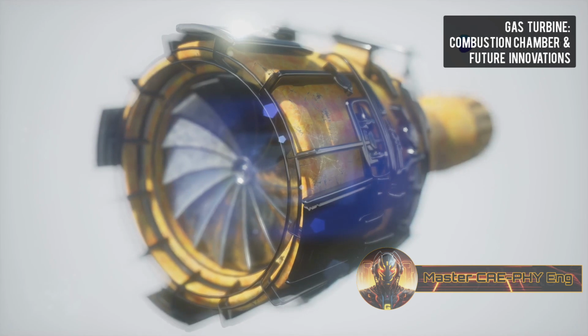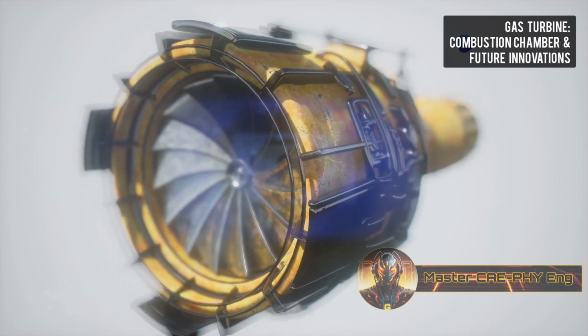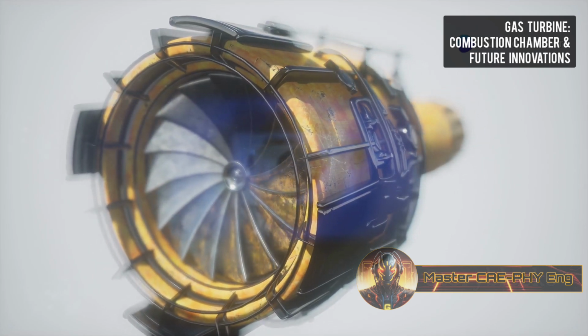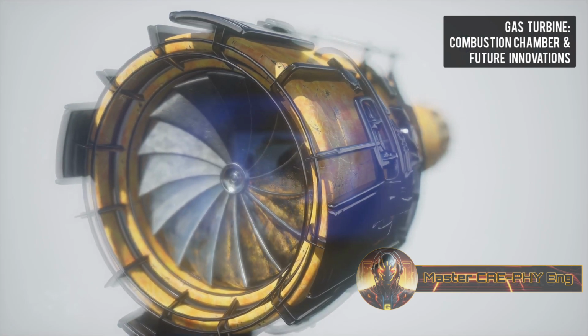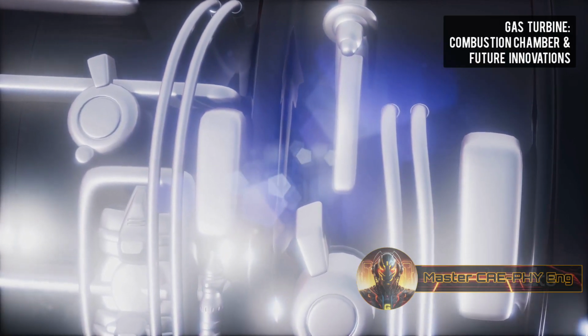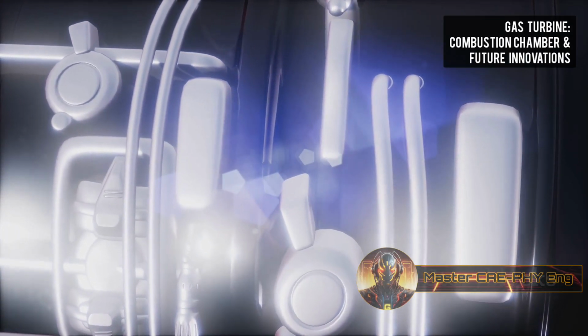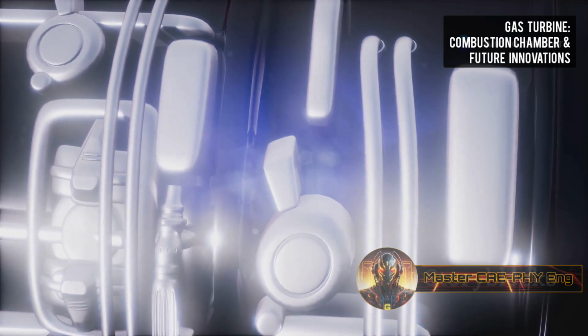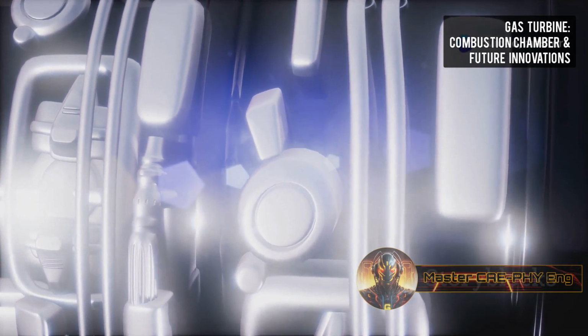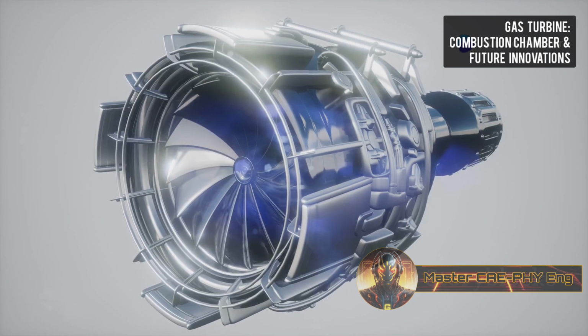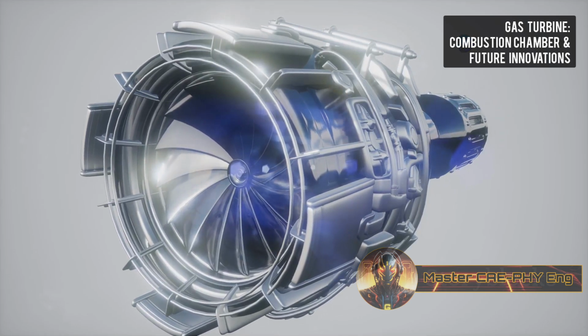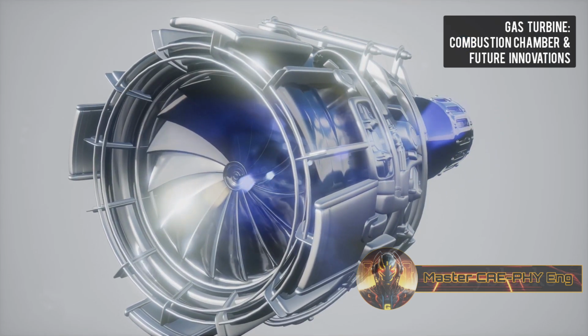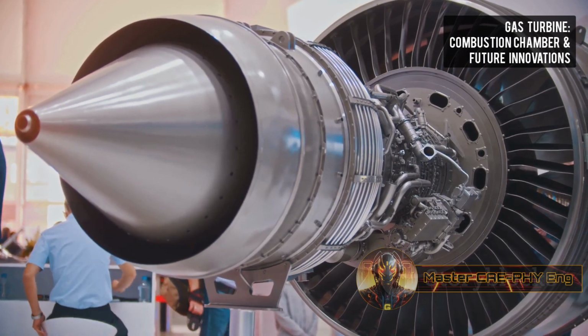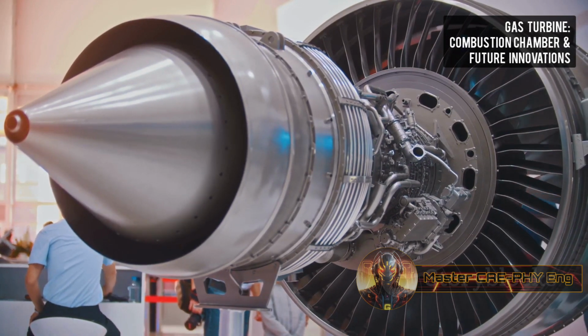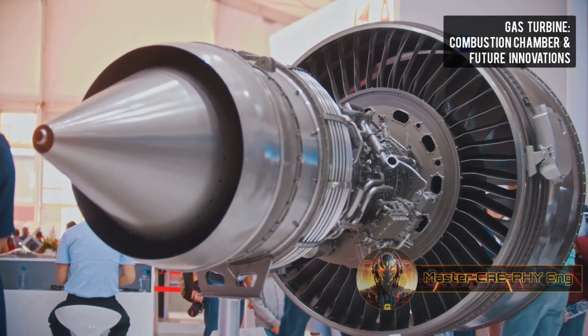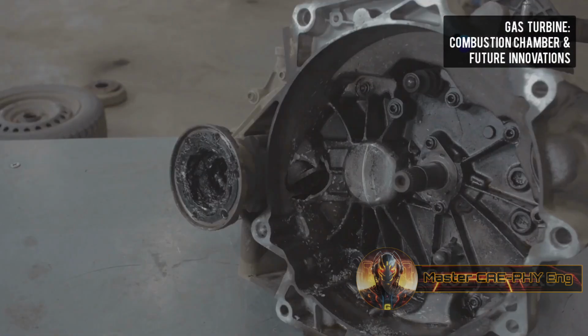The application of thermal barrier coatings, or TBCs, is another critical aspect of material strategy. TBCs are thin ceramic coatings, typically yttria-stabilized zirconia, applied to the hot gas side surfaces of combustor components. These coatings provide thermal insulation, reducing the metal temperature underneath. Cooling techniques are vital to keep the combustor wall temperatures within acceptable limits, ensuring the material's structural integrity.